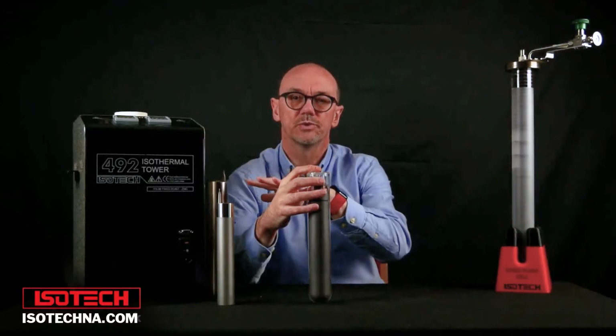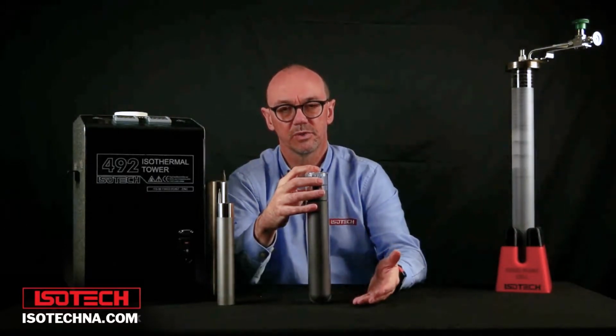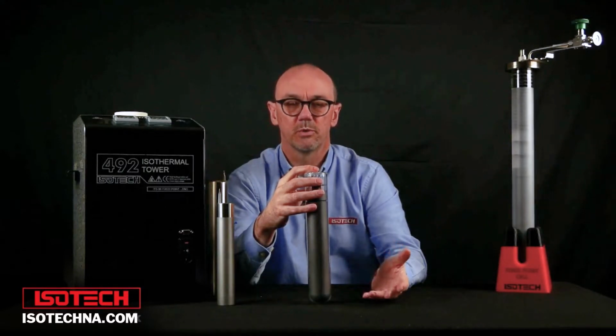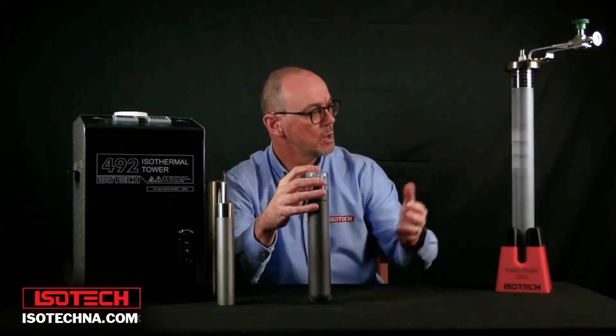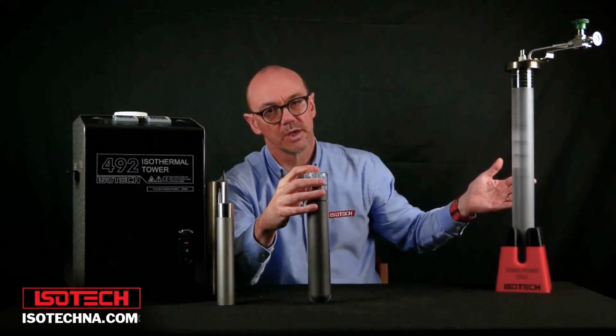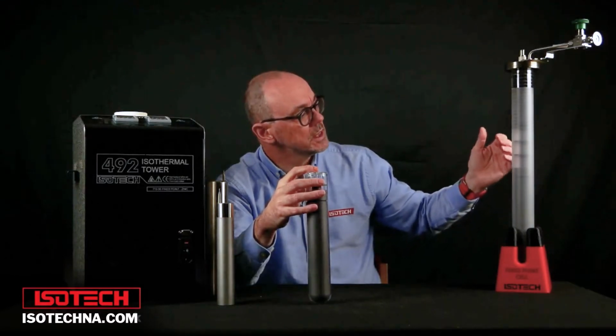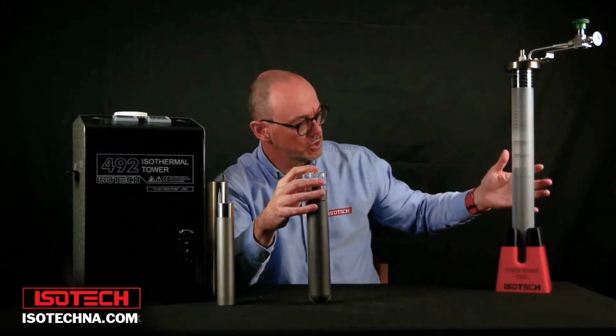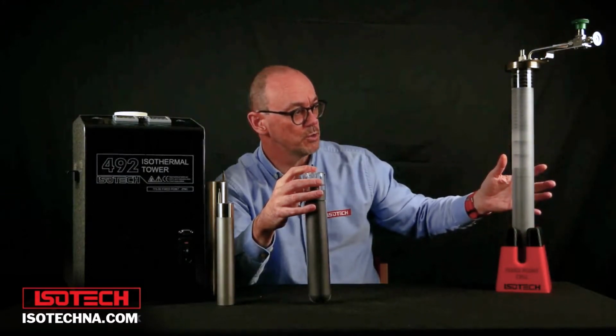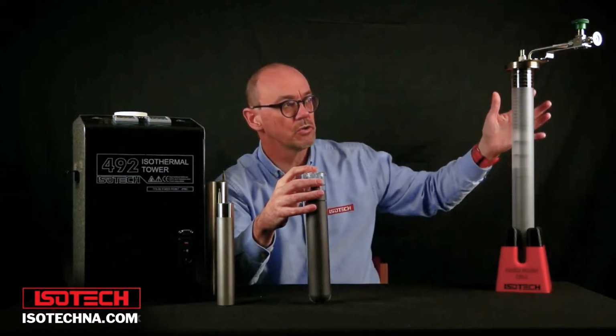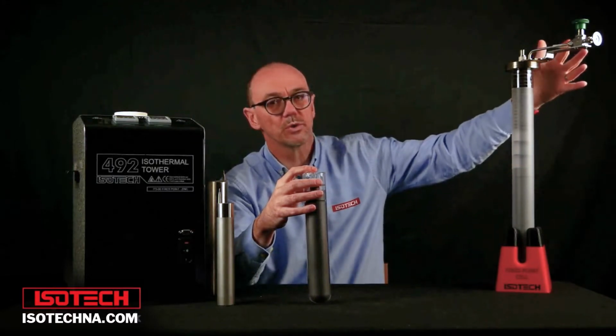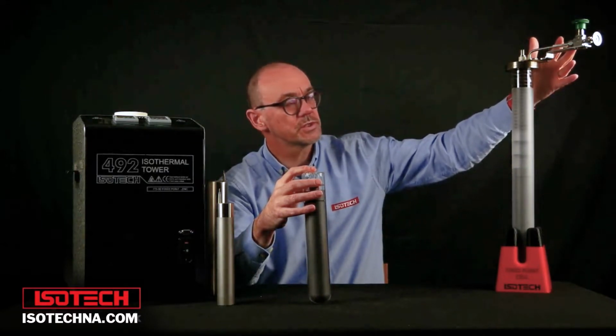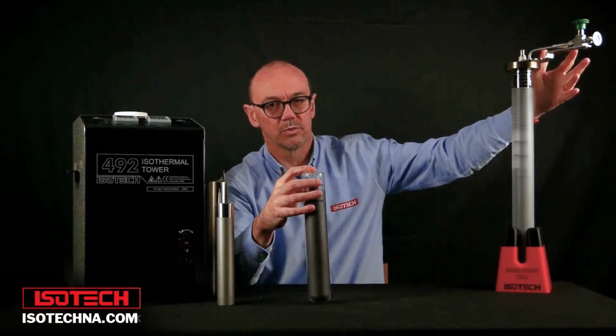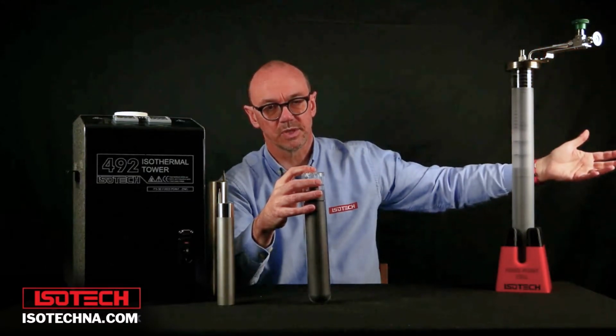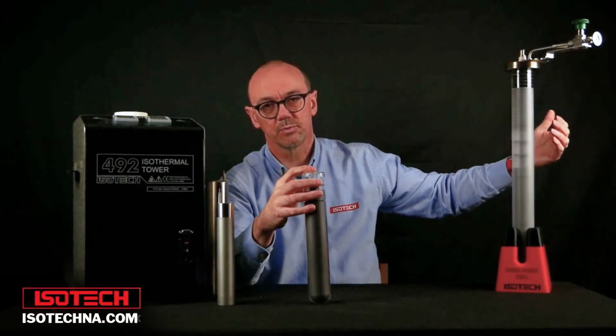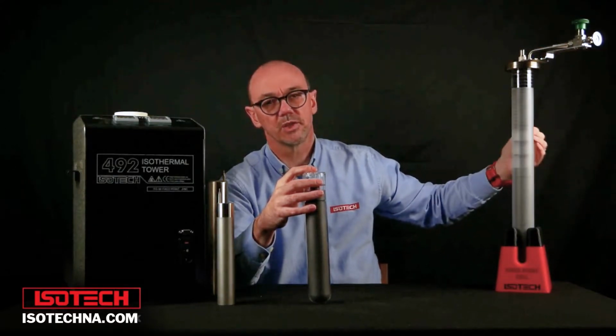So these cells are all sealed, and that makes them convenient to use, and the majority of cells in use are sealed cells. But this cell is an open cell, and what that means is it's a similar construction. We've got a graphite crucible with the pure metal, and you can see it's in this much longer glass tube, with this port here. So this would be connected to a manifold which would enable us to vacuum out the cell, then backfill it with an inert gas, and to set the pressure.